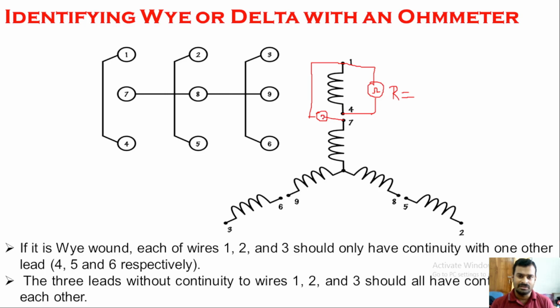So I'm going to measure the resistance here across 1 and 7. The resistance will be infinite. So what we have to do first is take any one terminal, connect it with the other terminals one by one and note down the resistance. Where you get a resistance, mark that particular terminal and keep it aside. Say if I measure the resistance across the different terminals, I will get a resistance value only between 1 and 4. Other values will be infinite: 1 and 7, 1 and 9, 1 and 6, 1 and 3, 1 and 8, 1 and 5, and 1 and 2, different combinations, but all the values will be infinite resistance except 1 and 4.